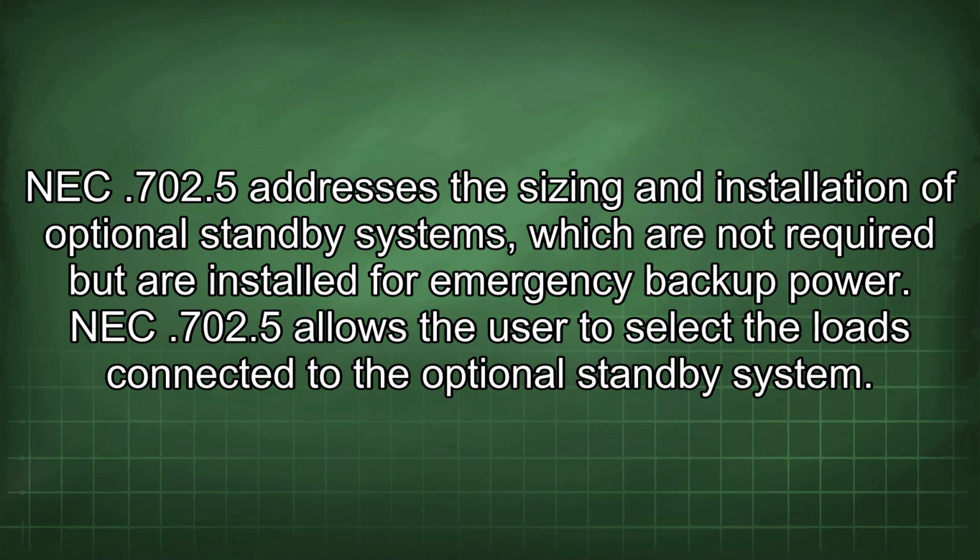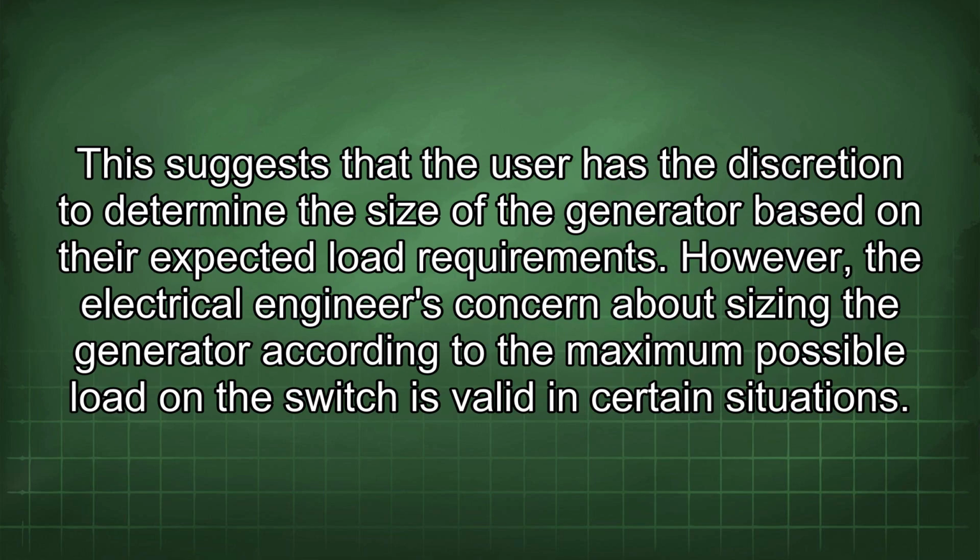NEC 702.5 addresses the sizing and installation of optional standby systems, which are not required but are installed for emergency backup power. NEC 702.5 allows the user to select the loads connected to the optional standby system. This suggests that the user has the discretion to determine the size of the generator based on their expected load requirements.